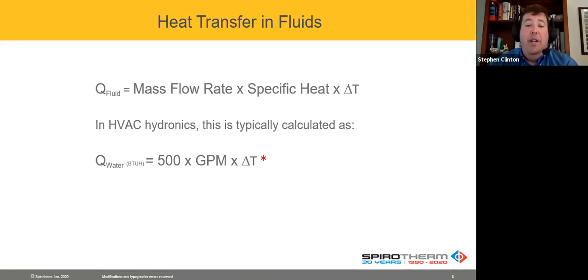So everybody's rounded up. You see the red asterisk there. That's very, very important because the red asterisk tells us that assumes an air-free system. Every load calculation program, every piece of software used to size every piece of equipment out there.